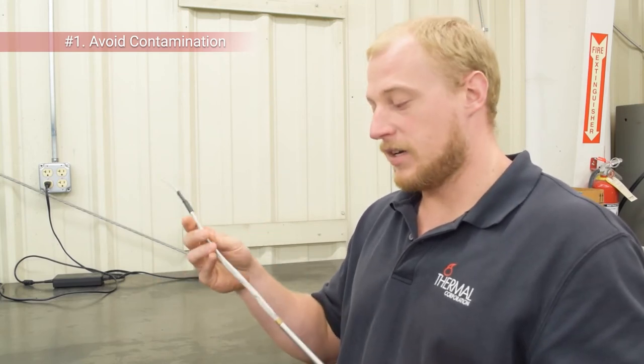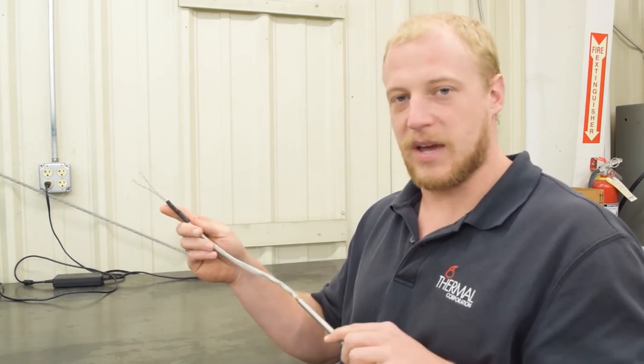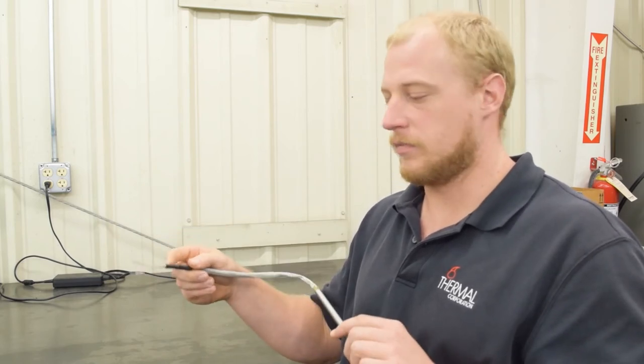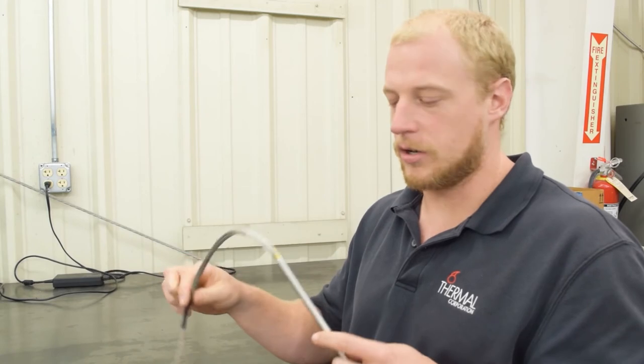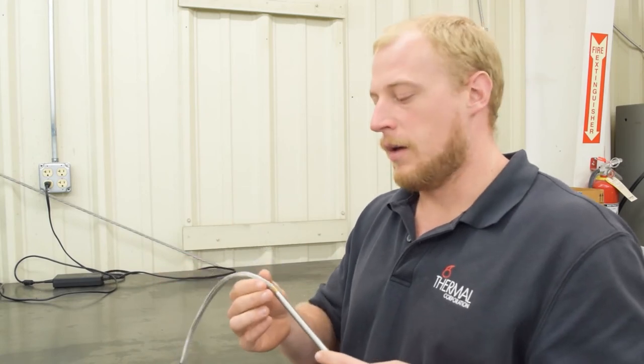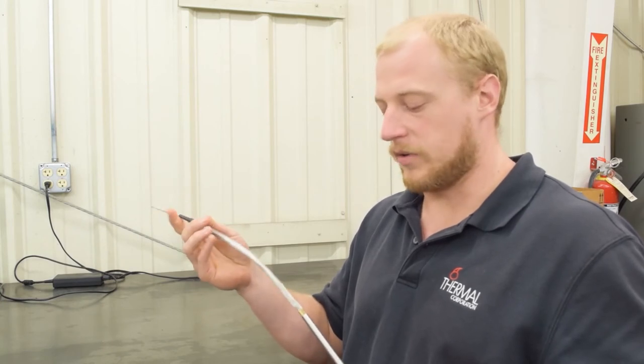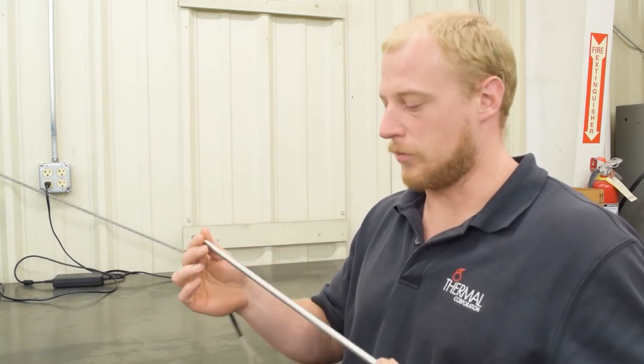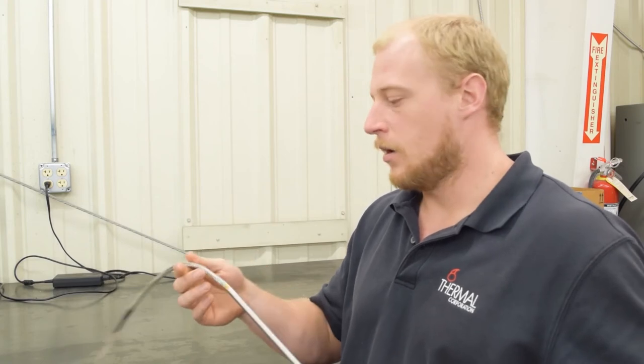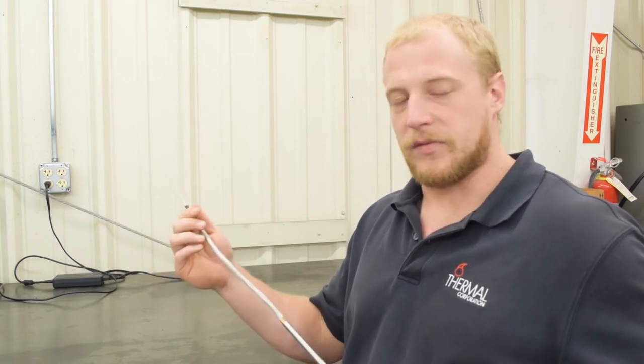If you do happen to get moisture on your heater or leads, you can bake these in an oven at 200 degrees for an hour or so and it should drive that moisture out. But definitely try to avoid getting plastic, oil, or any organic chemical or solvent on or around the leads or the end of the heater. That's the most common failure mode we see.